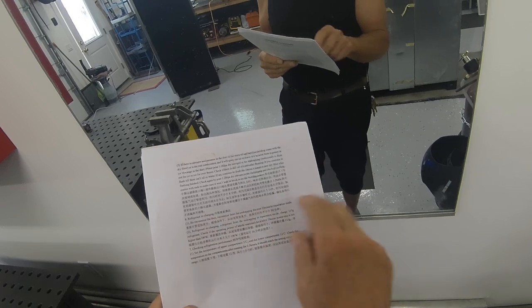There is a mention in the back, when it's talking about refrigerant recharging, that there could be oil or moisture in the system. So in the long run, I think it didn't have a leak - I think it just had a restriction, maybe clogged with oil, or maybe some moisture in there. Changing the dryer and weighing in the gas seemed to do the trick.